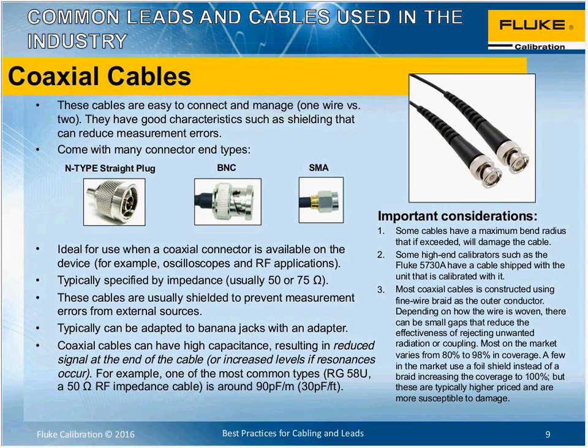I mentioned they're typically shielded, and there are different types of shielding that they use. Some of them have PVC, some of them have PTFE, which Paul will talk about here soon, but usually good shielding with these types of cables. The downfall is that these coaxial cables can have high capacitance, potentially reducing the signal at the end of the cable. As an example, one of the most common types of cables on the market is the RG58U, which has 50 ohm RF impedance, and typically it is about 90 picofarads per meter, so you need to consider that when you're looking at these cables.